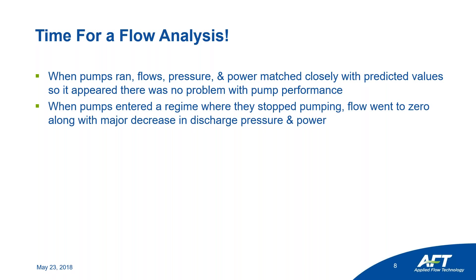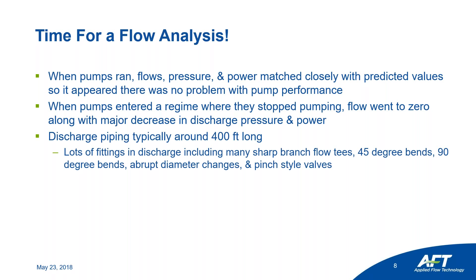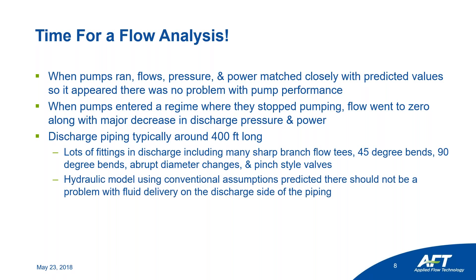However, there was a point where the pumps entered a flow regime and couldn't pump anymore — flow went to zero, with huge losses in pressure and power. They had lots of discharge piping, around 400 feet long, with many fittings: branch flow tees, elbows, diameter changes, several types of valves — lots of losses. When they modeled their minor losses with standard K-factor methods from handbooks or built into Fathom, the model showed there should not be a problem with fluid delivery on the discharge side.